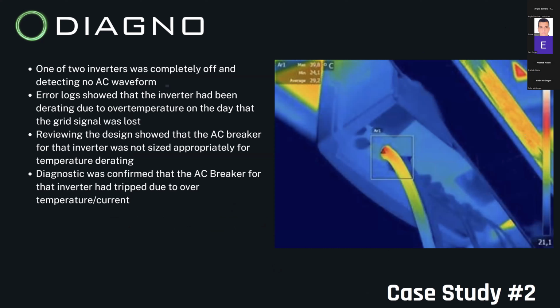And so one of the two inverters was completely off, of course, because that's what we had found via the generation profile. And again, the error log showed that the inverter had been derating due to overtemperature. When we reviewed the design, it showed that the AC breaker for that inverter was not sized appropriately for the temperature derating. And so we suspected that the AC breaker had just tripped off due to high current, high temperature at that particular time, due to the sizing of that breaker.